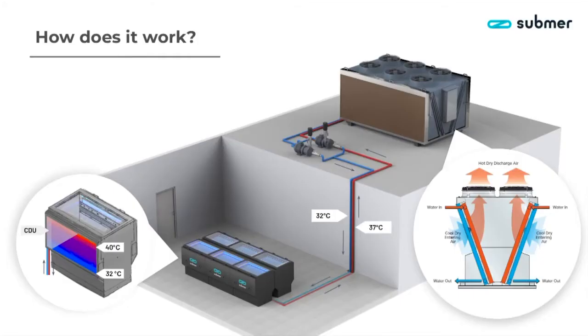And how specifically does immersion cooling work? Well, it's changing the medium, as I mentioned. Essentially, instead of air, we use a liquid which is non-conductive, capturing the heat from the IT equipment and transferring that heat to a water loop, which takes the energy outside of the building or allows for energy reuse. Because it operates at very high temperatures, meaning an immersion system will typically run at between 50 and 60 degrees centigrade, the water loop temperatures are also in a similar range.